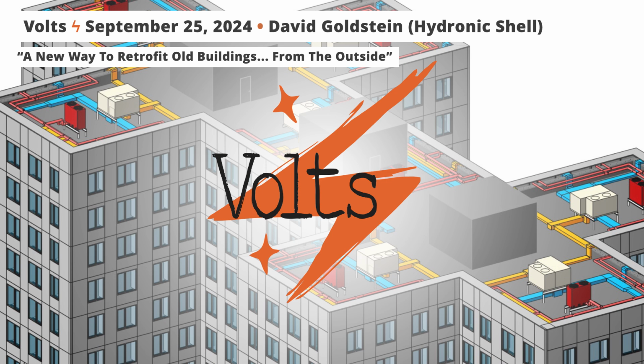Conveniently, we're already delivering dehumidified ventilation to each apartment through ducts sitting in the facade. So we just take a little bit of air off that ductwork and supply it directly into the facade cavity, effectively dehumidifying it. It only takes a small amount of air, because the space isn't a large volume, and there aren't constant moisture loads pushing into it. A small amount of dehumidified ventilation air can keep that space nice and dry.